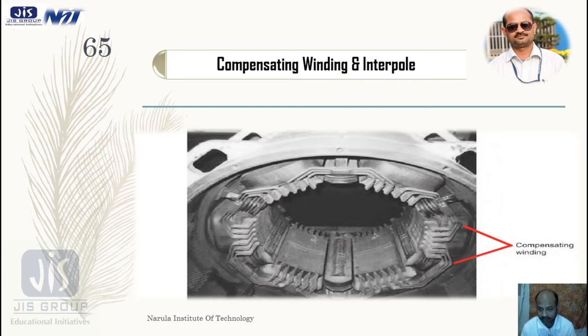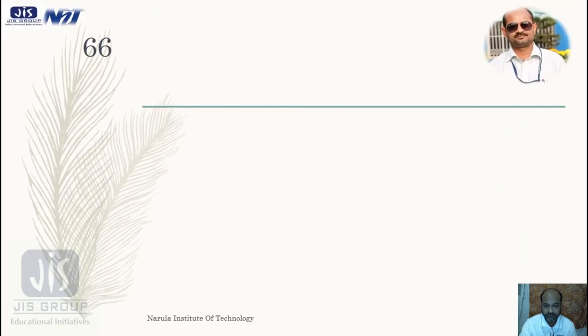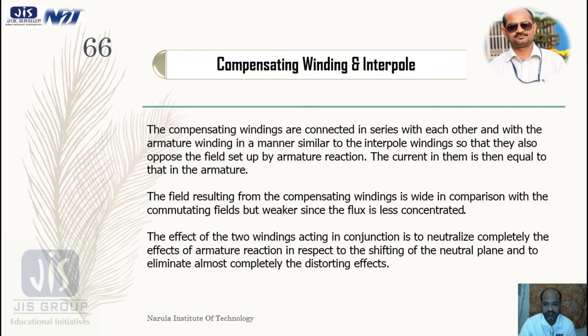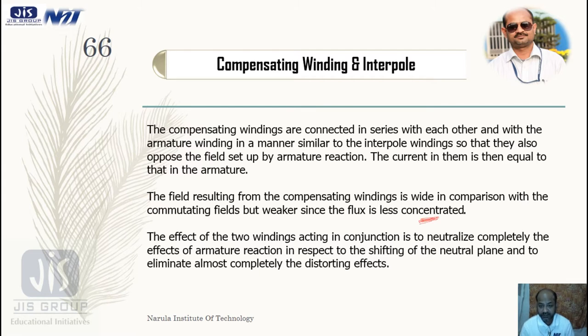In the main pole faces this compensating winding is used. Because this compensating winding carries current in the reverse direction, the field produced by it opposes the field set up by the armature reaction, since they carry current equal to the armature current. The compensating winding is wider in comparison with the commutating field, but weaker since the flux is less concentrated. The effect of the two windings acting in conjunction is to neutralize completely the effect of armature reaction with respect to the shifting of the neutral plane and to eliminate almost completely the distorting effect.